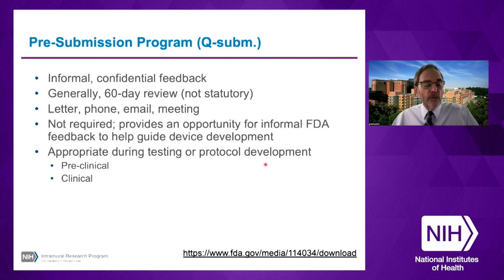And this can happen in any number of ways, by letter, phone call, email. Perhaps the most productive way is a face-to-face meeting, which are usually about an hour. These are not required, but it gives you an opportunity to get informal FDA feedback to help guide device development. And this can be appropriate at any stage of the testing or protocol development. It might be preclinical, when you're designing, let's say you have bench testing about mechanical stability. It might be about your preclinical bench work. If you're developing a pivotal animal safety study, it might be before that. And if you're going into a clinical trial, it can include that as well as marketing.